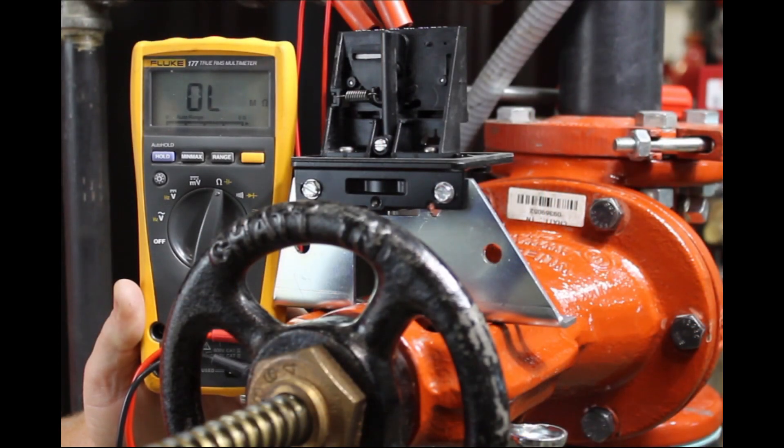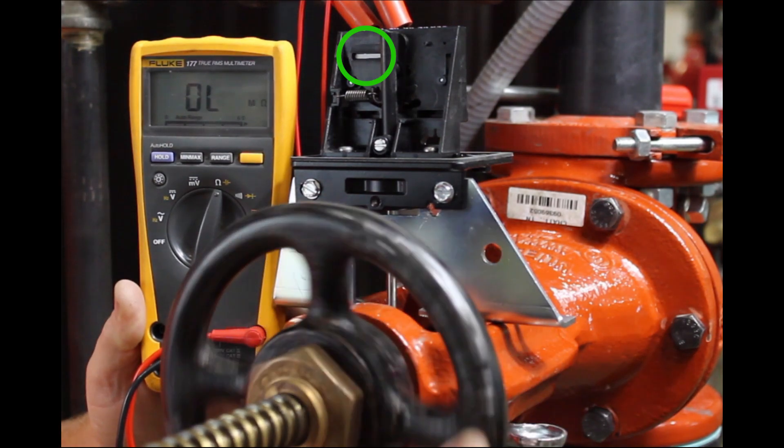Final adjustment is correct when the OS&Y activates within the first two revolutions of the hand wheel as the valve is being closed.